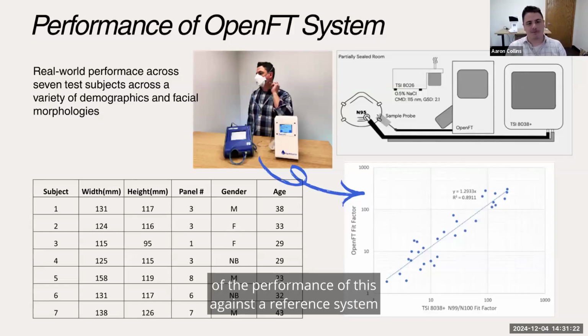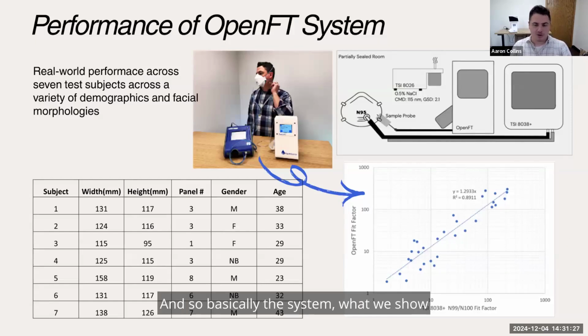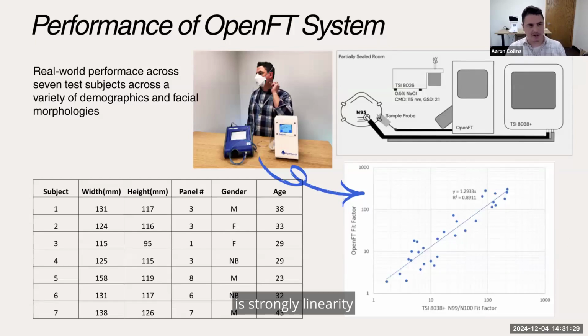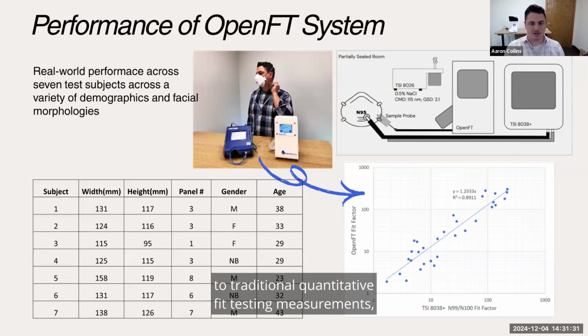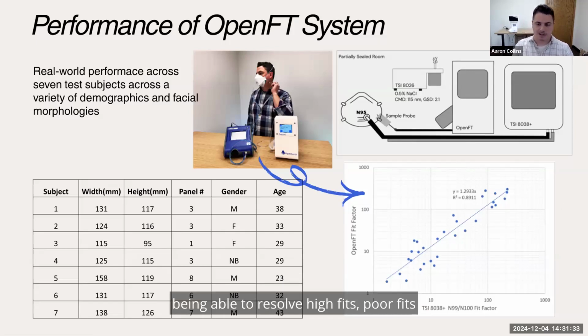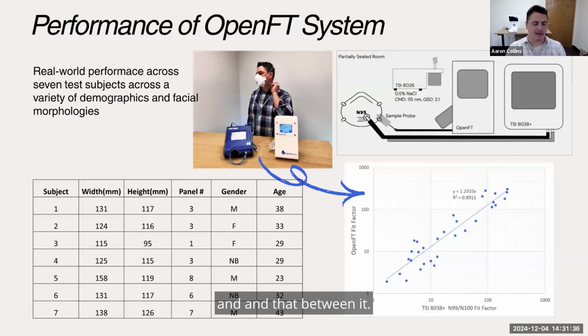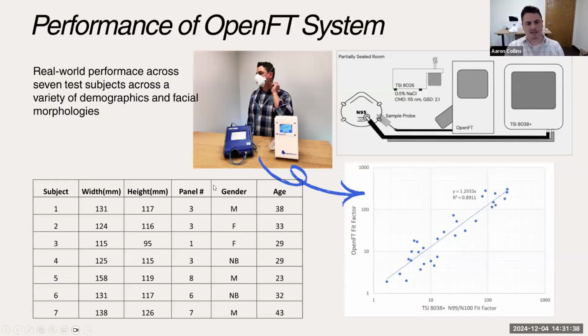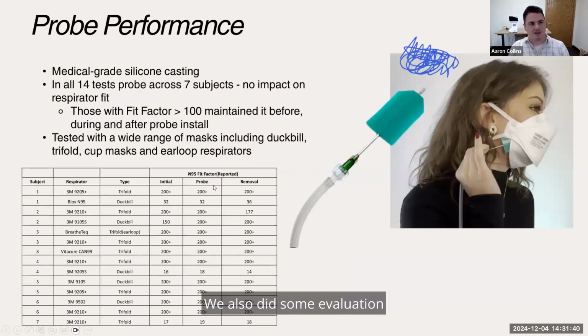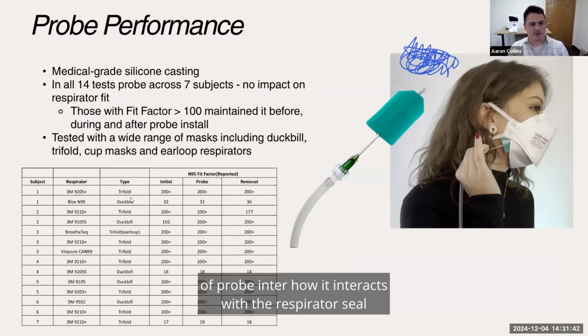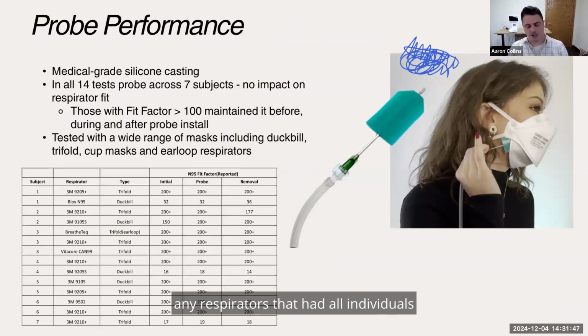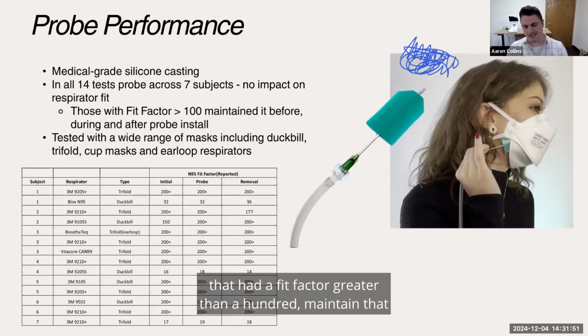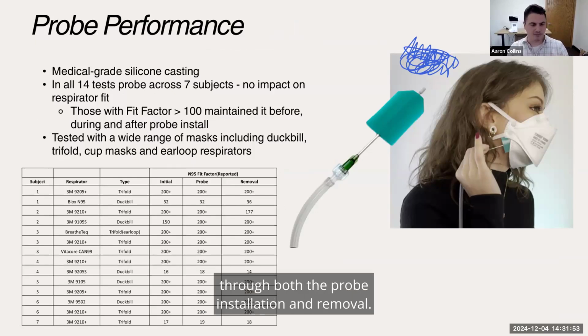So we've also done some evaluation of the performance of this against a reference system on a 7-subject panel. And so basically what we show is strong linearity to traditional quantitative fit testing measurements, being able to resolve high fits, poor fits, and that between. We'll go to the next slide. We also did some evaluation of how the probe interacts with the respirator seal, and for the test that we did on a 7-subject panel, all individuals that had a fit factor greater than 100 maintained that through both the probe installation and removal.